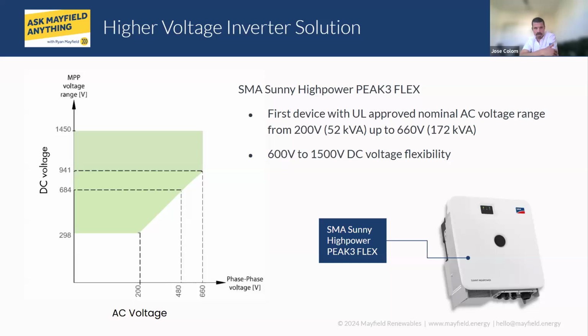The relationship we're seeing here is roughly a 1.4 to 1.5 multiplier from the AC to the DC. The reason I bring up these values is because the 1.55 refers to the minimum voltage input for operation, or the starting voltage for operation of the inverter. And then the 1.40 will be the minimum voltage in the MPPT window for that AC voltage reference. So for example, if we take the 480, you multiply that by 1.55, that gives you the starting voltage of the inverter. The 1.4 will be the lower end of the MPP voltage range.